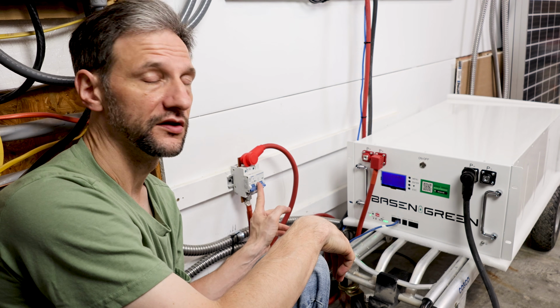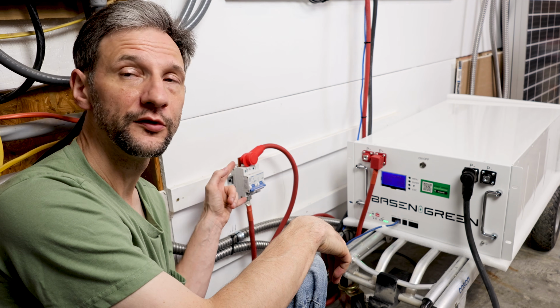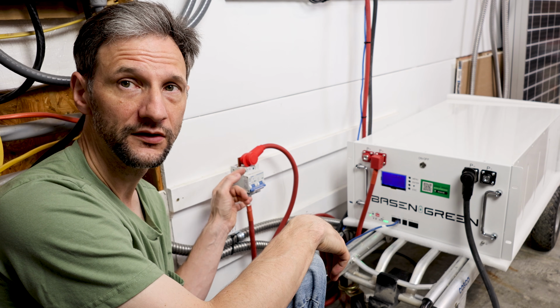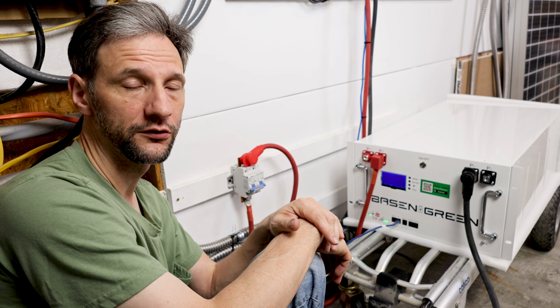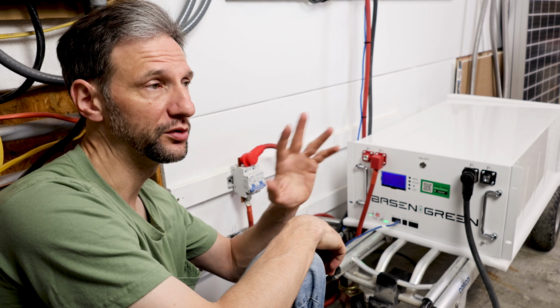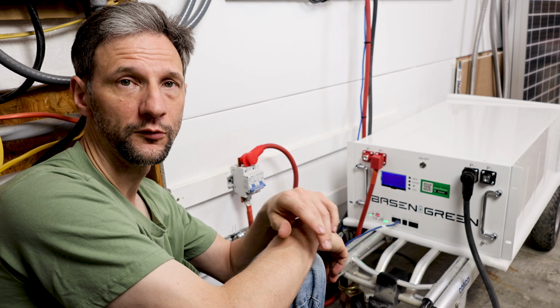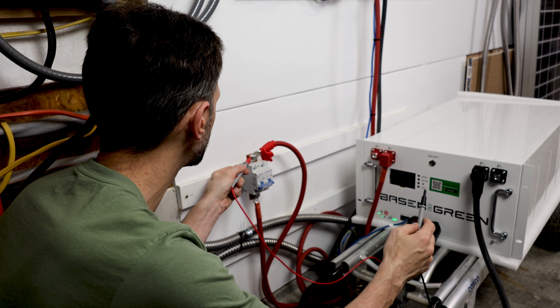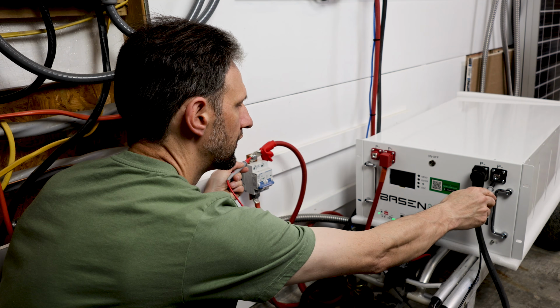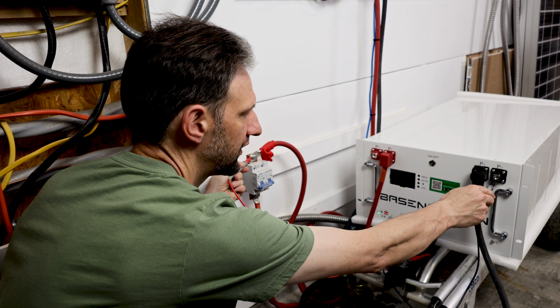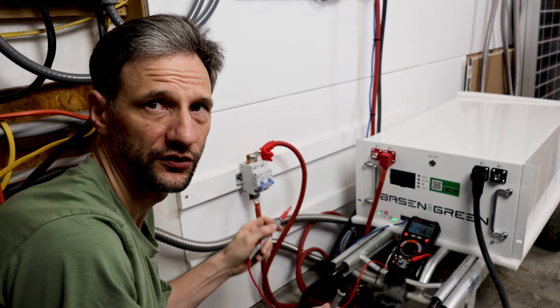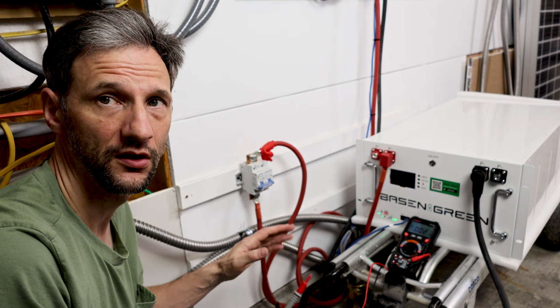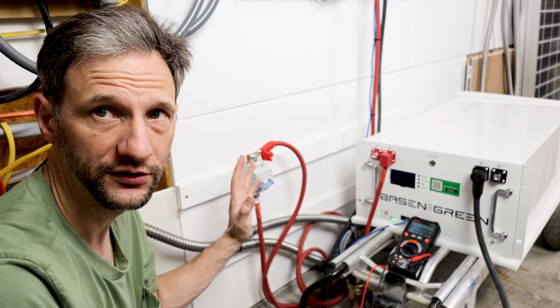Otherwise, before connecting this breaker, I would need to cross these terminals with a pre-charge resistor for about 10 seconds, to make sure the capacitors were charged up before we flipped the breaker. Otherwise, I'd put a tremendous amount of current through the system very quickly. I can measure the inverter side voltage, and it's at 44, 45, 50 - so the inverter's holding 50 volts on the terminal, meaning I don't have to pre-charge the resistor.